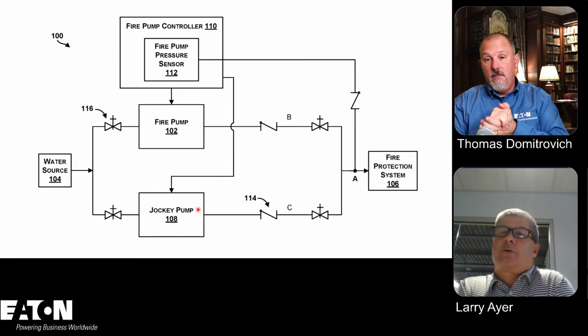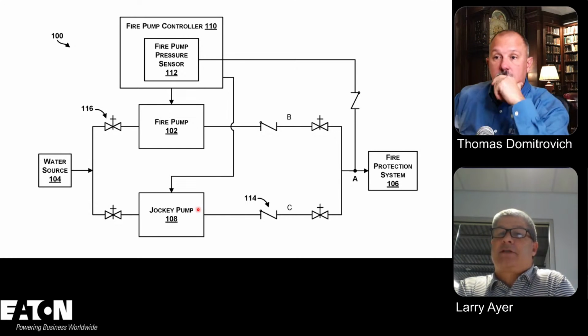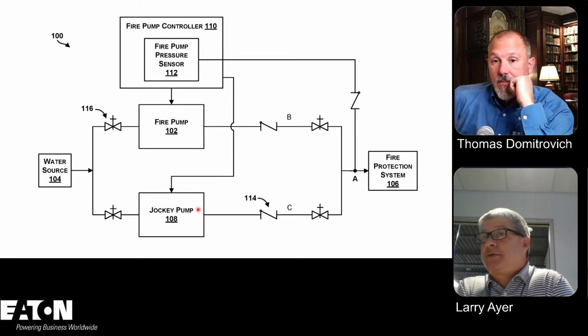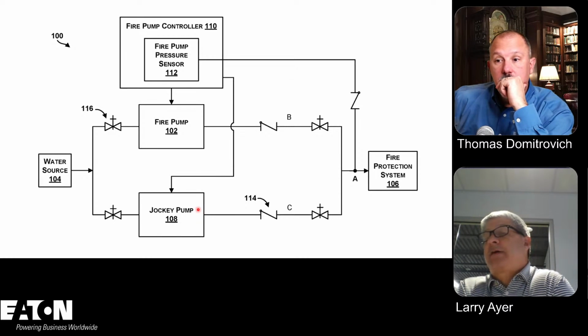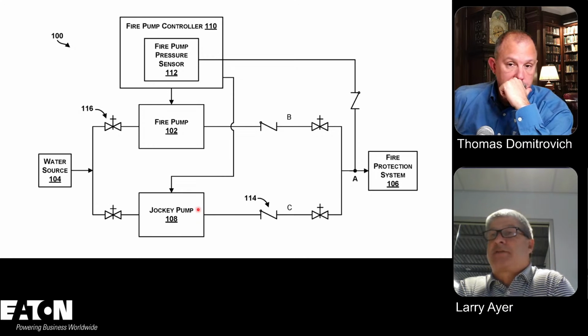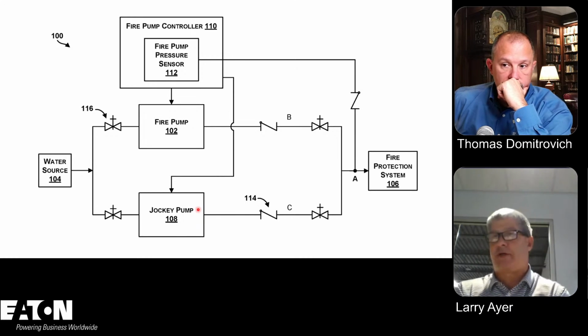That's a good question. What you sometimes see is jockey pumps tapped off the actual fire pump feeder. You're allowed to do that. I've seen fire pumps fed out of a separate panel. I've seen fire pumps fed out of just a generator-backed-up panel. So I've seen it in various different ways. There's really nothing in the code that says it has to be on the same feeder.